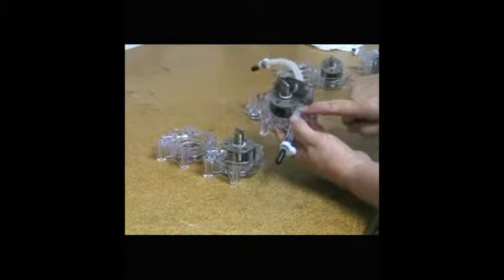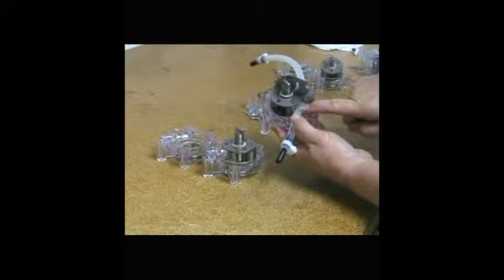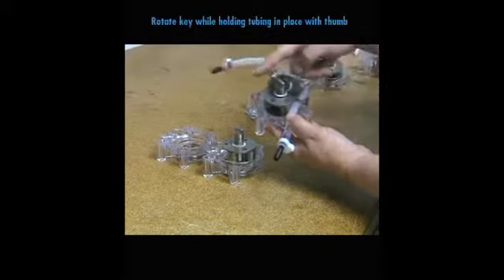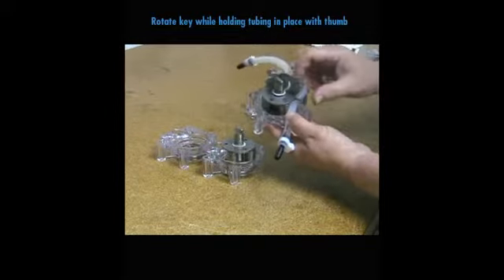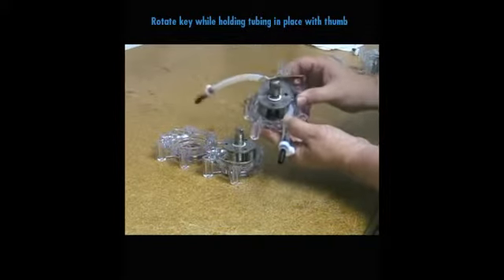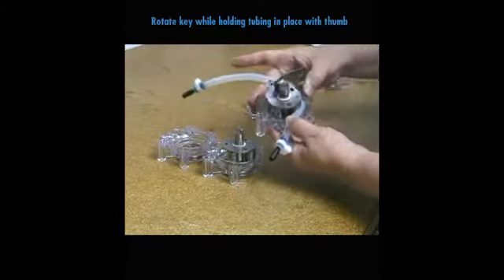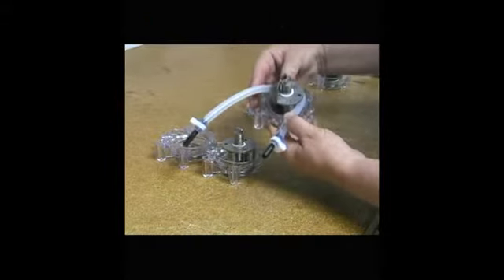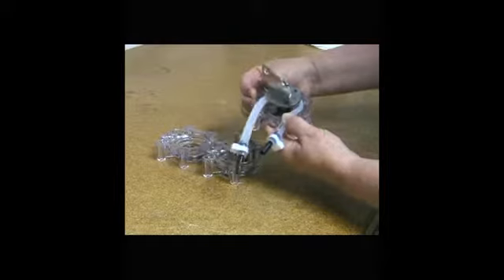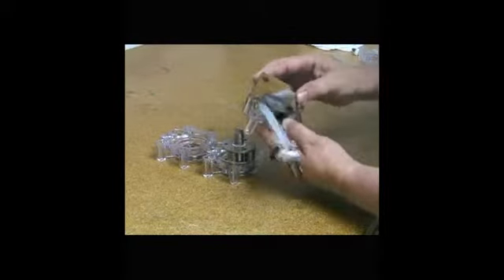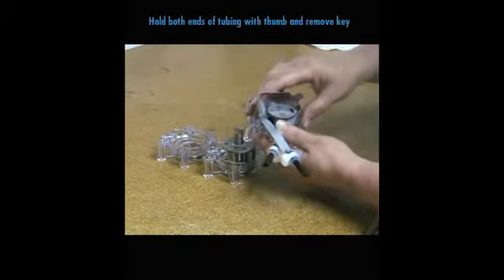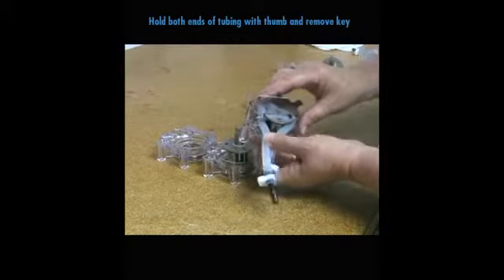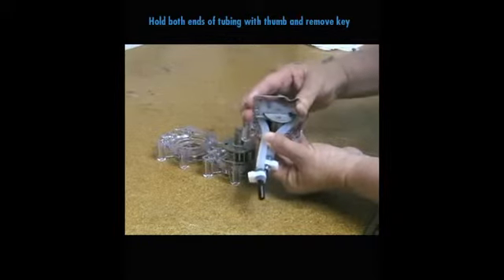Notice how the key presses the tubing into the housing. Now I'm going to start turning this key all the way to the other side while holding the tubing in place with my thumb. I'm going to use the key. It's going to press the tubing uniformly into the pump. Now I'm going to move my thumb over slightly. I'm going to remove the key.